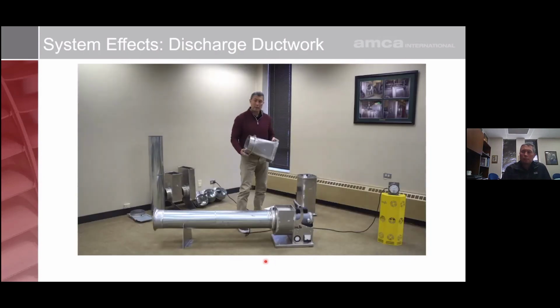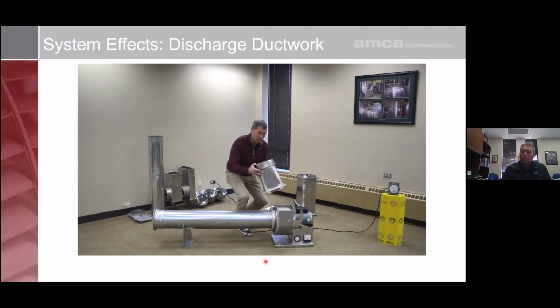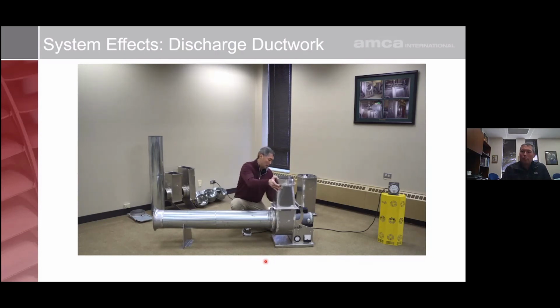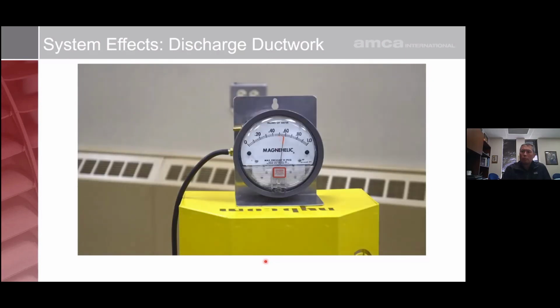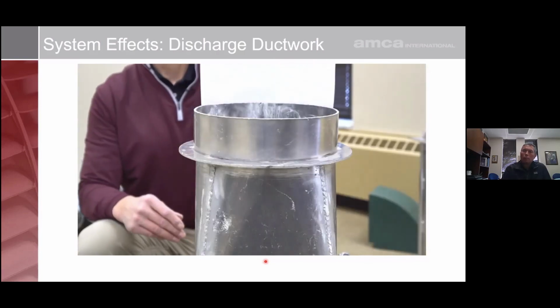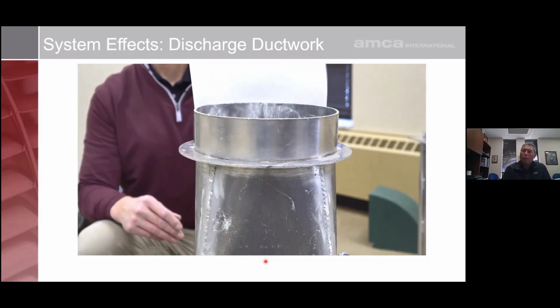So if we take this rectangular to round transition, the same one that we used when we were doing the inlet measurements, and put it on the outlet of the fan, and again, no turning devices inside of it. Put it on the outlet. Notice that there is, again, an increase in performance when we look at the magnehelic gauge. And if I take the same piece of paper, notice that even in this short distance here, we've already started to get some evening out of the velocity profile.